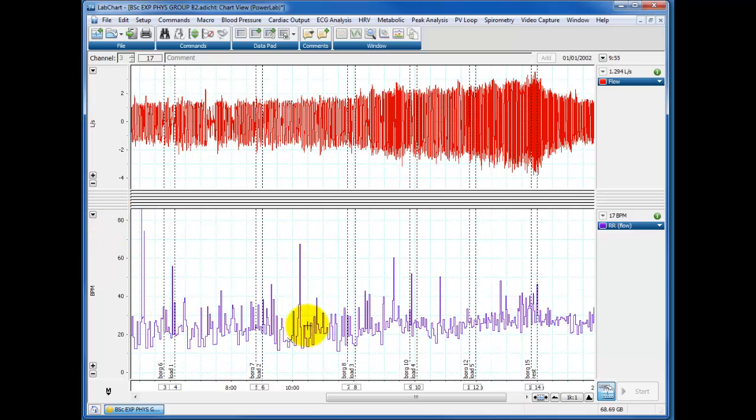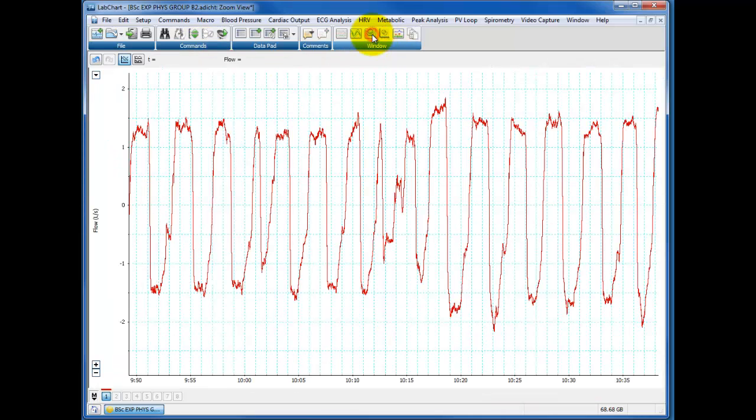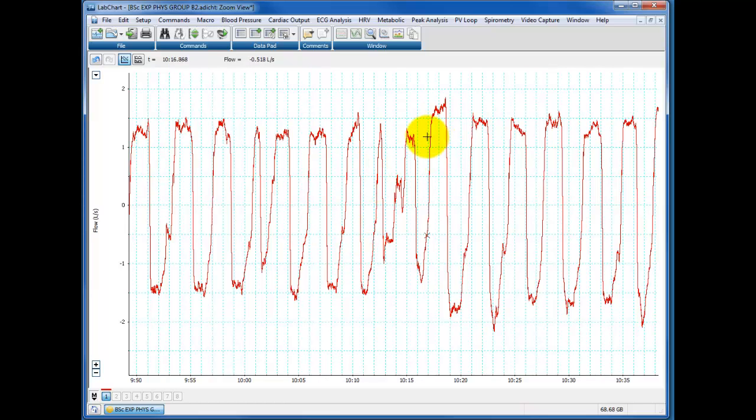There are some spikes in here and look at this huge increase in respiratory rate. Let's just zoom in on this area here and have a quick look and lo and behold there's a double breath, in fact there's a triple breath here where the subject has taken a quick intake of breath and it's counted that as three breaths so that would explain those data.